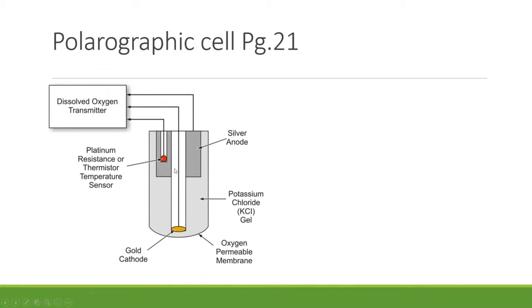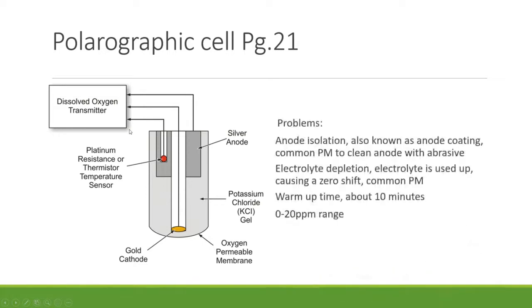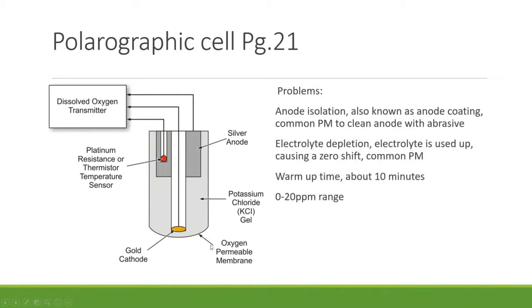A more realistic view of the polarographic cell shows all components in one housing: silver anode, KCl fill fluid, oxygen-permeable membrane, gold cathode, and temperature compensation. Common problems include anode coating — cleaned with a mild abrasive such as a cotton cloth or paper towel as a PM task — and electrolyte depletion, which causes a zero shift. In modern practice, cells are typically replaced rather than refilled.